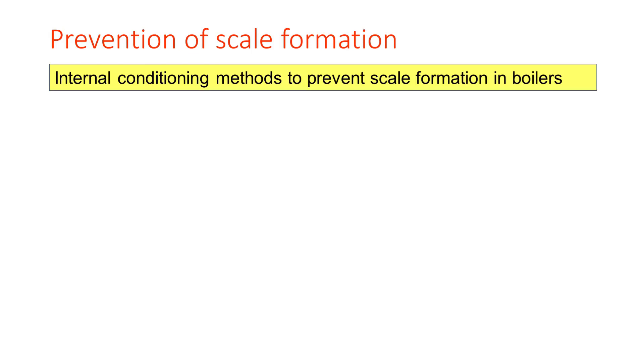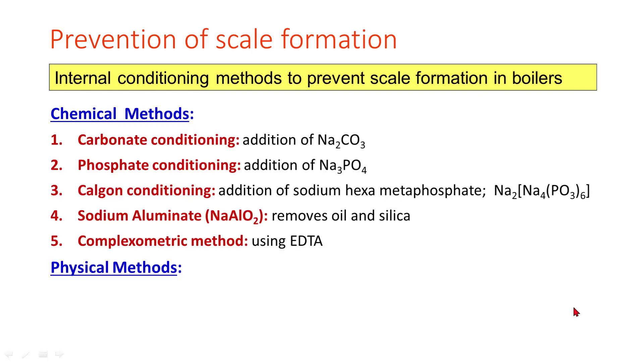Internal conditioning methods to prevent scale formation in boilers involve chemical and physical methods. Chemical methods include carbonate conditioning by the addition of sodium carbonate, phosphate conditioning by the addition of sodium phosphate, calgon conditioning by the addition of sodium hexametaphosphate, sodium aluminate to remove oil and silica, and the complexometric method using EDTA — ethylenediamine tetraacetic acid.